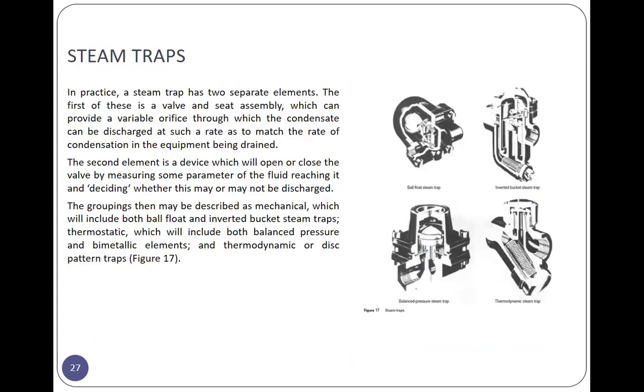Okay. Now for the steam traps, which are the most important part of steam piping. In practice, a steam trap has two separate elements. The first is a valve and seat assembly, which provides a variable orifice through which the condensate can discharge at such a rate as to match the rate of condensation in the equipment being drained. The second element is a device which will open or close the valve by measuring some parameter of the fluid, sensing it, and deciding whether or not it may be discharged. The groupings may be described as mechanical, which include both ball float and inverted bucket steam traps; thermostatic, which include both balanced pressure and bimetallic elements; and the thermodynamic or disc pattern trap.